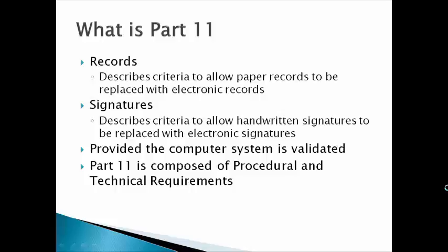Part 11 is composed of procedural and technical requirements, and we will discuss both. Many companies go to outside companies to purchase a Part 11 compliant program. They should keep in mind that these purchased programs can only satisfy the technical requirements — the computer system requirements. They cannot satisfy the procedural requirements; these must be implemented by the purchasing company. And we'll discuss what's involved with that.